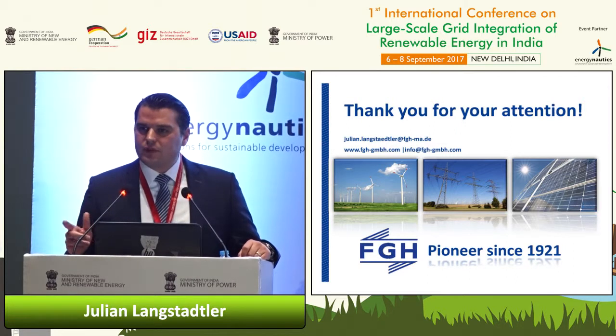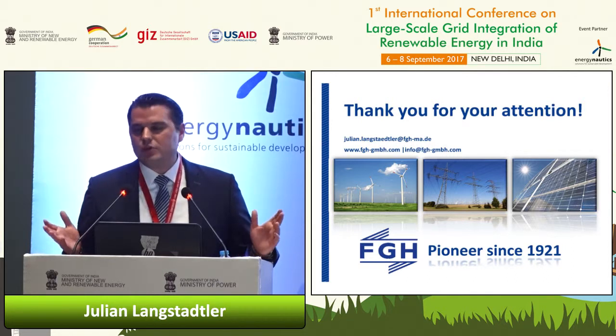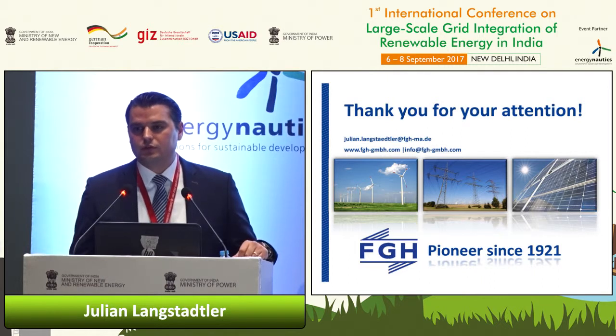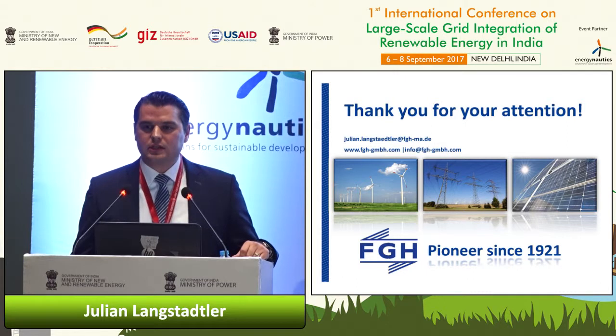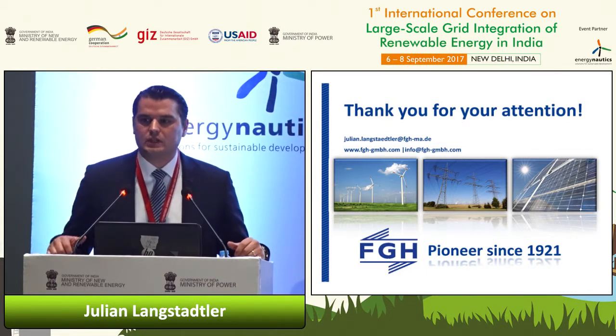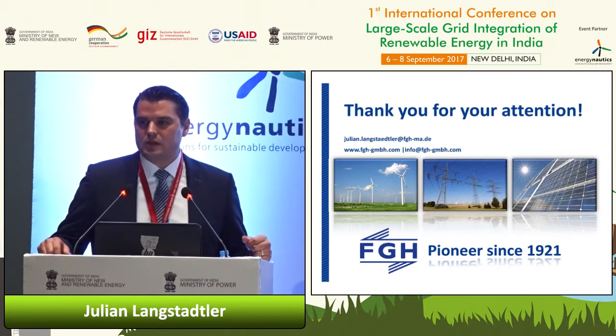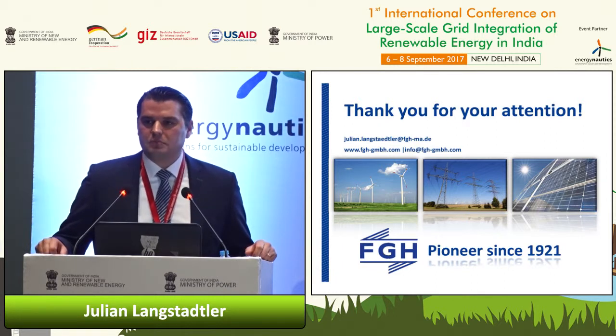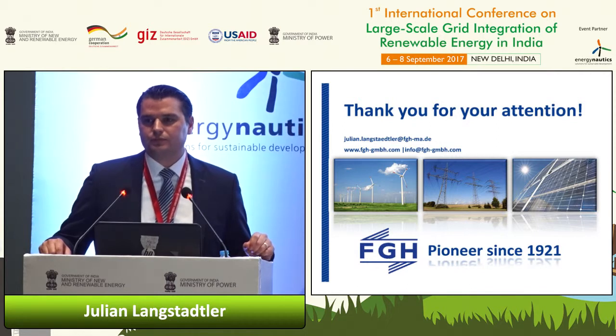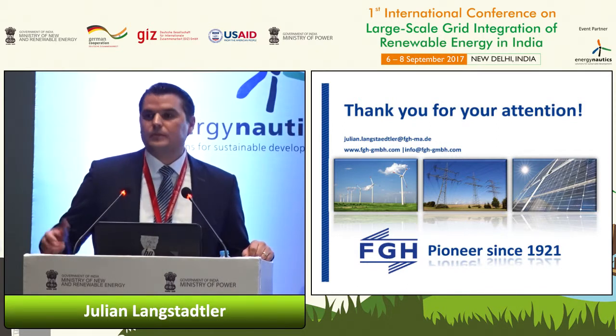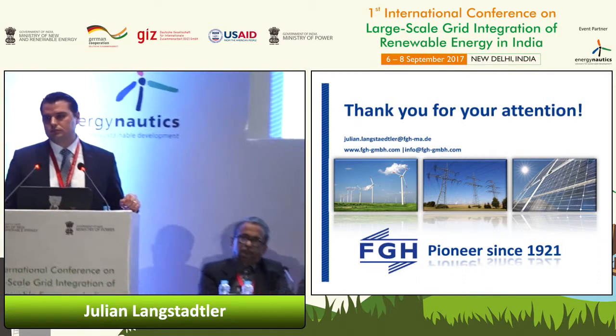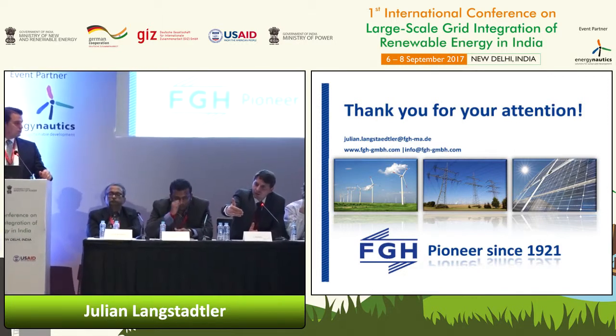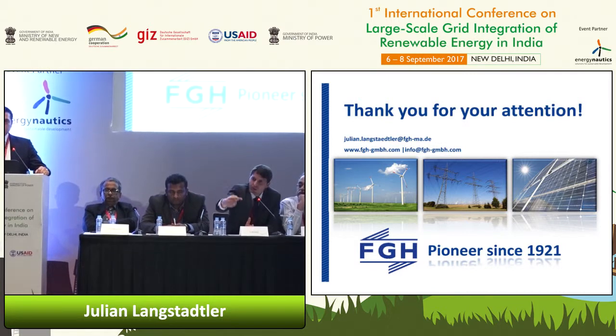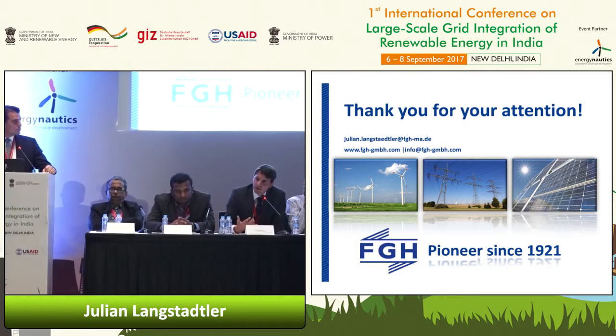Another reason is maybe also that you have the interaction with the system itself. I'm not sure whether this is done properly with a converter solution. This is more or less an island. And if there is some interaction with the system itself, and we often see that within measurement campaigns, effects that are not directly describable, I'm not sure whether you can emulate them with the converter. So it's quite commonly used for PV inverters, for inverters which attach to the grid with a PLL, so it's okay. But if you look towards synchronous generators, I also have my doubts that this works fine, because you don't have the feedback loop, where the synchronous generator feeding into the grid has an impact on the grid. That's what we have at least seen in our measurements. Exactly. But maybe it has to be a case-by-case investigation.